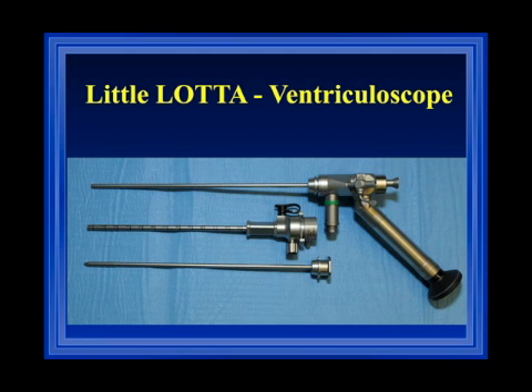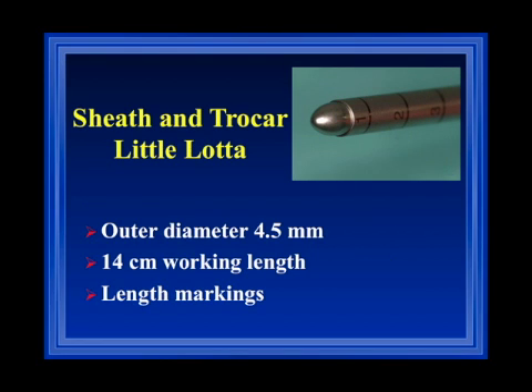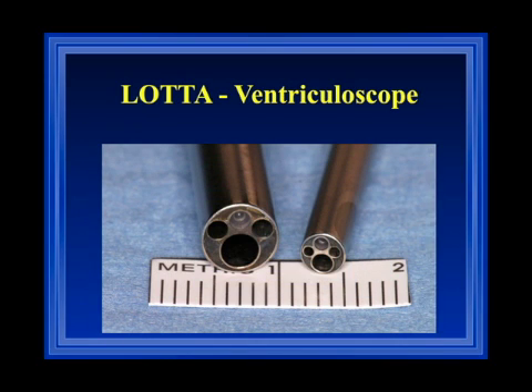The little LOTTA scope has the same basic design. Its outer diameter is 3.6 millimeters, with a rod lens of 1.2 millimeters and a 1.6 millimeter working channel, plus two side channels with a diameter of 1 millimeter. The outer diameter of the trocar is 4.5 millimeters, and therefore we can use the little LOTTA system in newborns, premature newborns, or in adults who have a small foramen of Monro.